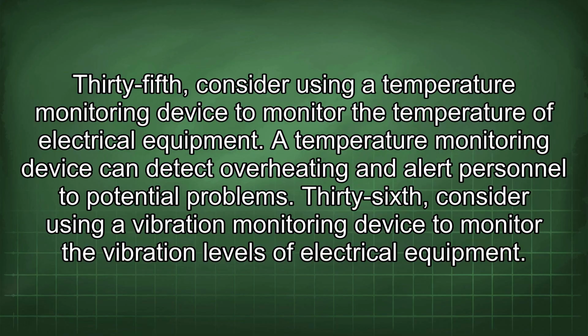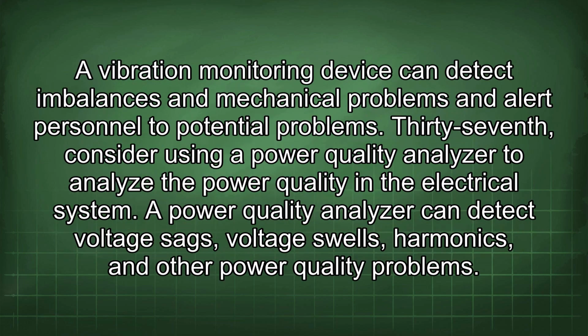36th, consider using a vibration monitoring device to monitor the vibration levels of electrical equipment. A vibration monitoring device can detect imbalances and mechanical problems and alert personnel to potential problems. 37th, consider using a power quality analyzer to analyze the power quality in the electrical system. A power quality analyzer can detect voltage sags, voltage swells, harmonics, and other power quality problems.